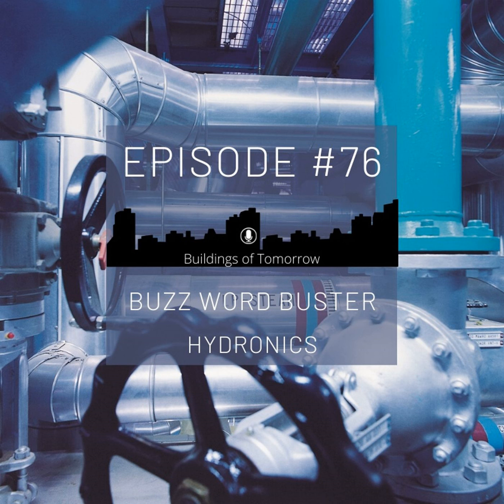Beautiful. Thank you. So we have the next word, which is also a PICV related one, probably on the other end of the scale to a certain extent, delta P min. Yes. So as the term says, pressure independent refers to this differential pressure controller, which is a mechanical setup within this complete control valve. And for this differential pressure controller, it is necessary that the pump provides a minimum pressure. This is kind of the driving force of the differential pressure controller. And this is, in addition to the maximum flow that needs to be calculated and considered, the other key value that needs to be taken into consideration. The delta P min is what we have to make sure is always available at this PICV, because then it works properly.